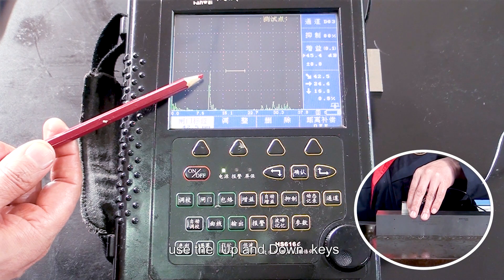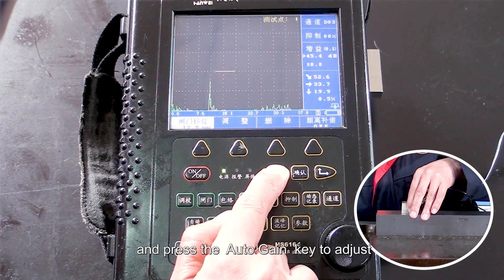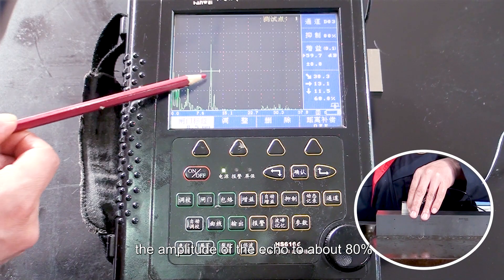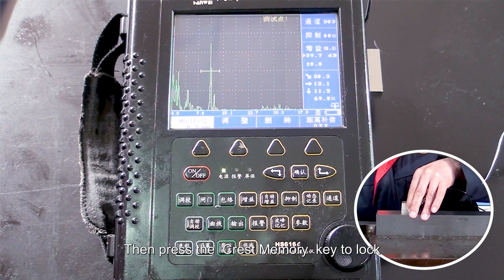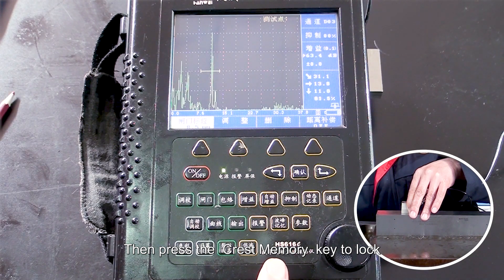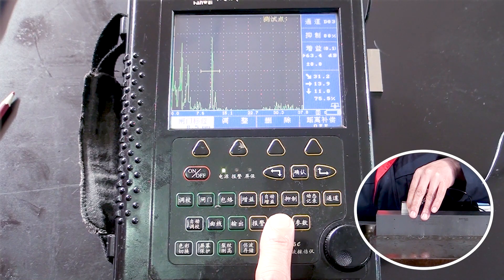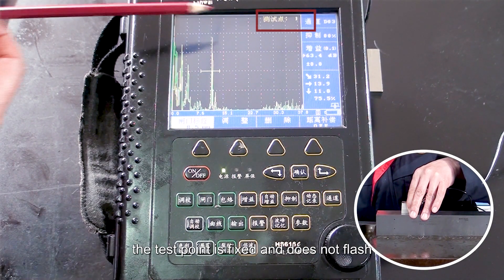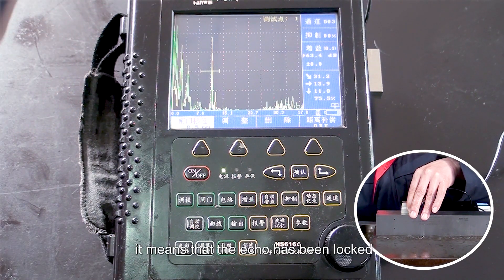Use the up and down keys to move the gate to cover the echo, and press the auto-gain key to adjust the multiplier of the echo to about 80%. Then press the peak memory key to lock the maximum echo in the gate. When the number behind the test point is fixed and does not flash, it means that the echo has been locked.